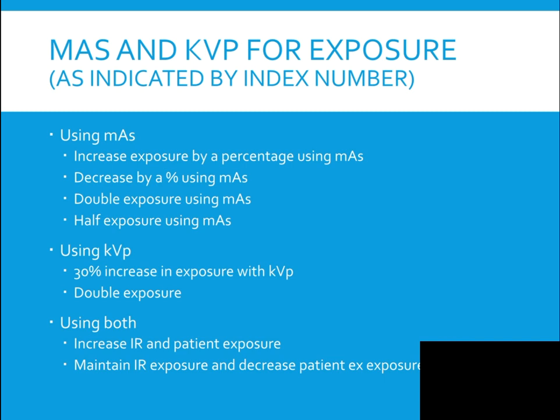This is a bit of hyperbole, but if you shot a hand and you used a full-sized image receptor and you didn't collimate, then your index number is going to be based on all that direct exposure plus a little bit of exposure to the hand. So it's going to show probably that you greatly overexposed the patient when you may have used the perfect set of technical factors.